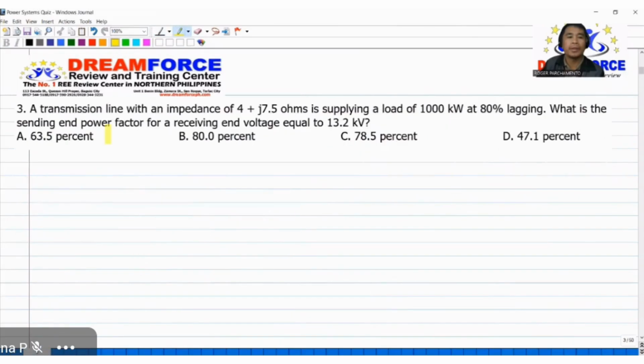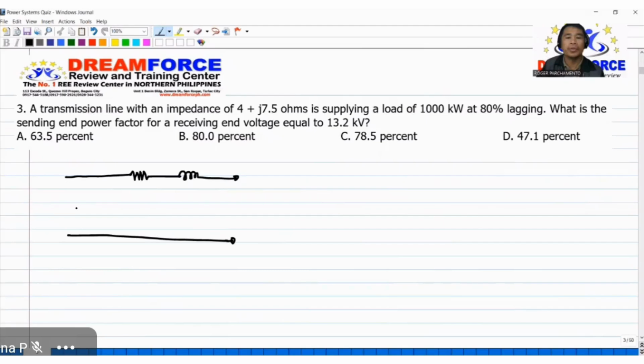So next, number 3. A transmission line with an impedance of 4 plus j7.5 ohms is supplying a load of 1,000 kilowatts at 80% lagging. So what is the sending end power factor for a receiving end voltage equal to 13.2 kilovolts? We have here the transmission line with a resistance and reactance, supplying a load, and sending end. What is the sending end power factor for a receiving end voltage of 13.2 kV?